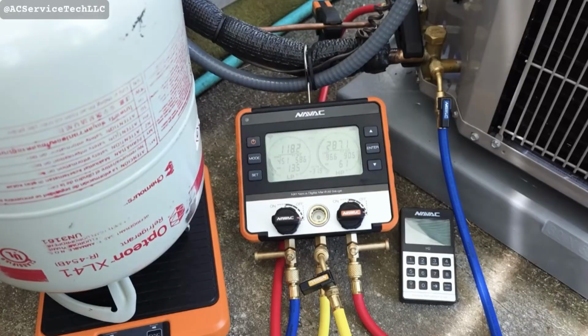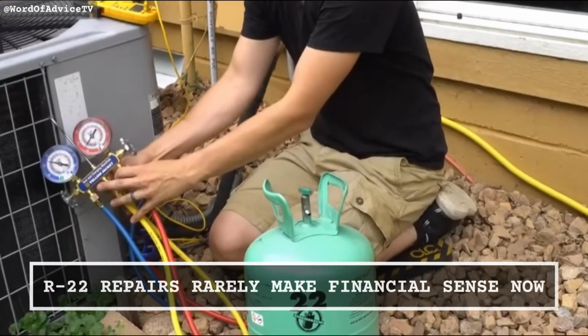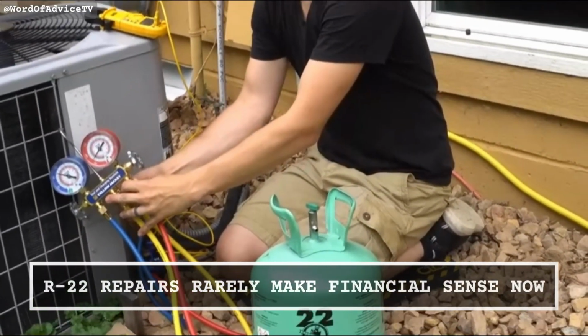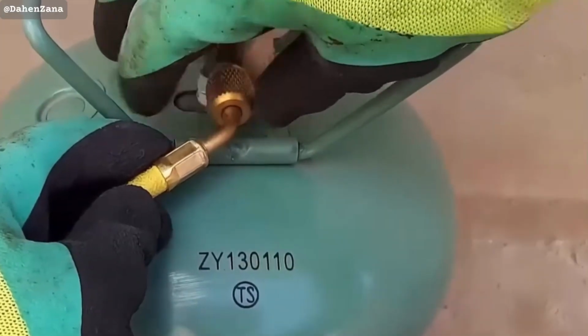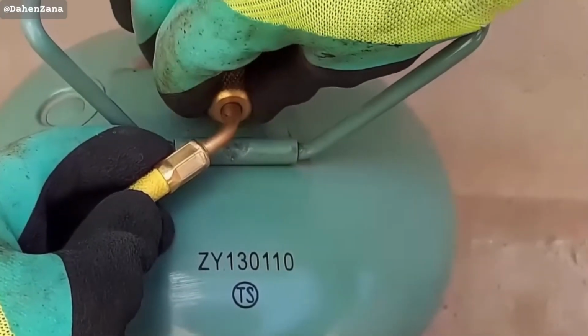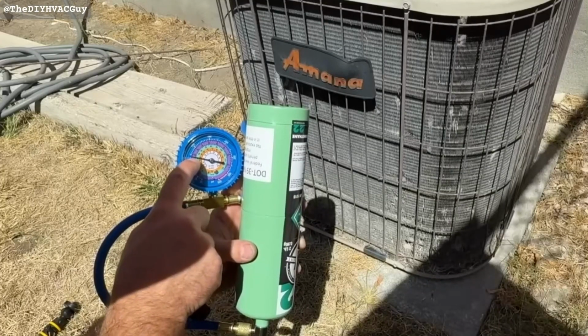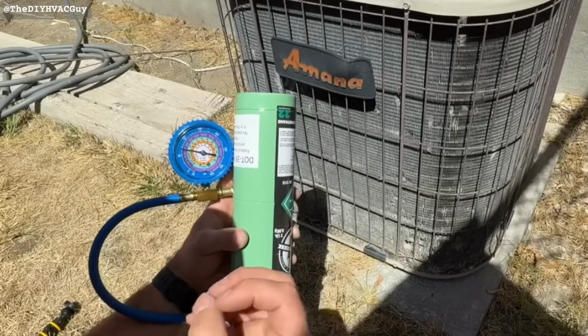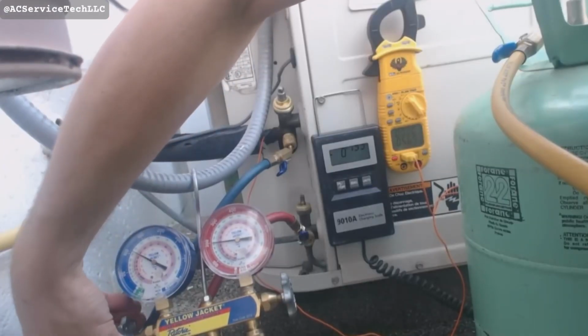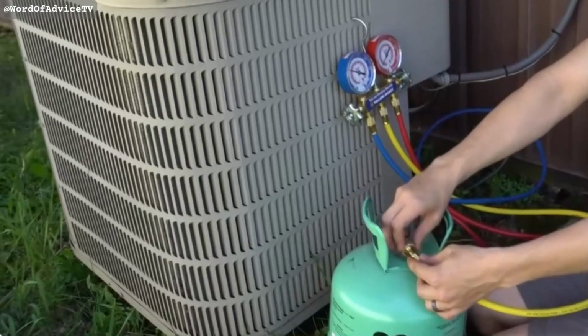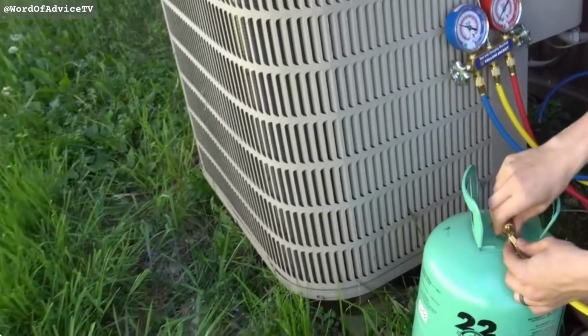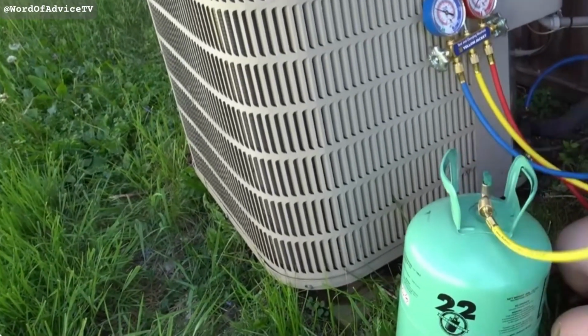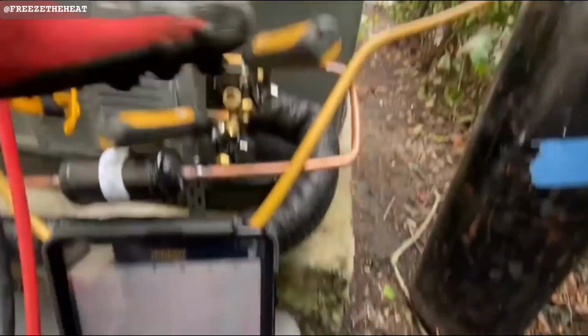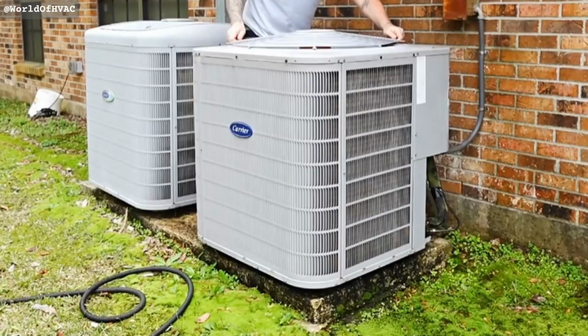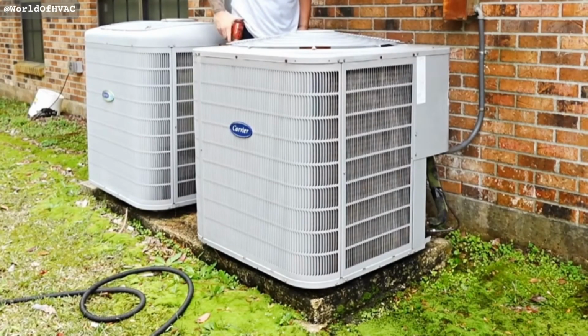Number 21. If you still have an R22 system, the math on repair versus replace has shifted hard. R22 was phased out under the Clean Air Act and current pricing runs about $150 a pound, sometimes higher. A typical 3-ton recharge needs 6 to 8 pounds, plus labor, plus a leak repair. One service call easily hits $1,500. 2 more in the same year, and you've spent the down payment on a new system. At that pricing, end-of-season replacement during October through February in southern climates almost always wins.